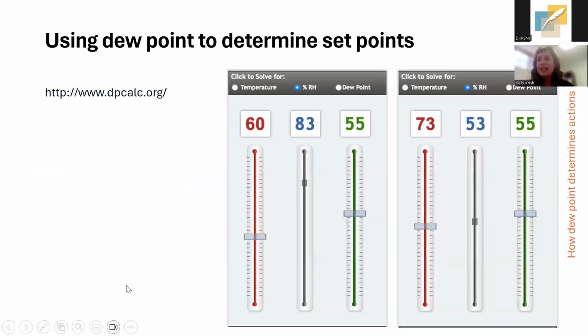So going back to this idea of the dew point calculation and giving this visual. If I knew that I had a 55-degree dew point, higher than 50, I know I'm looking at trying to balance some options between temperature and relative humidity. If I drop my temperature all the way down to 60, I'm going to say that's way too high a relative humidity. I can't have 83% in my space. So you might gradually increase that temperature until your RH is brought down to an acceptable limit. Let's say I wanted to stay below 55 in this example. Then I could say, okay, the lowest temperature I can achieve and still have a relative humidity below 55 is 73 degrees. So that might be my summer set point.